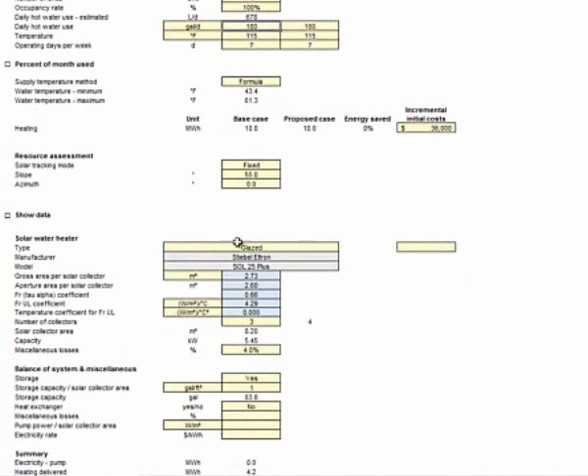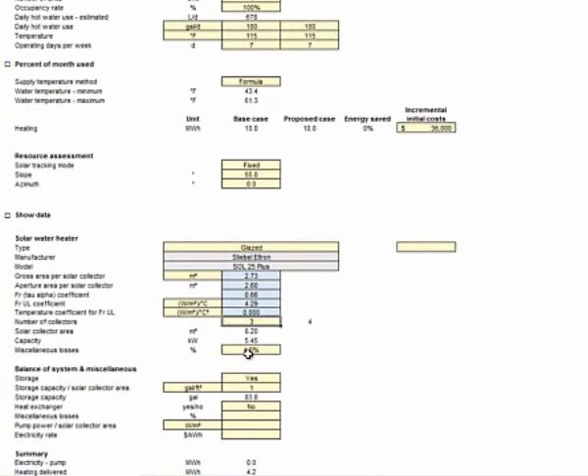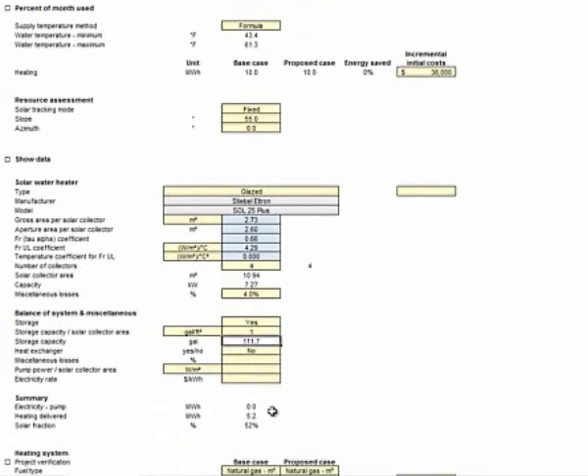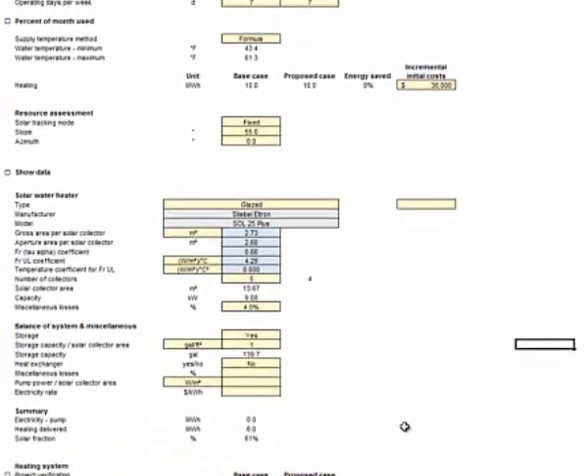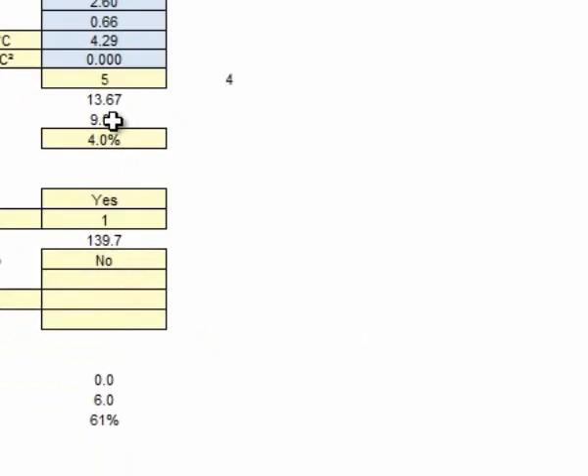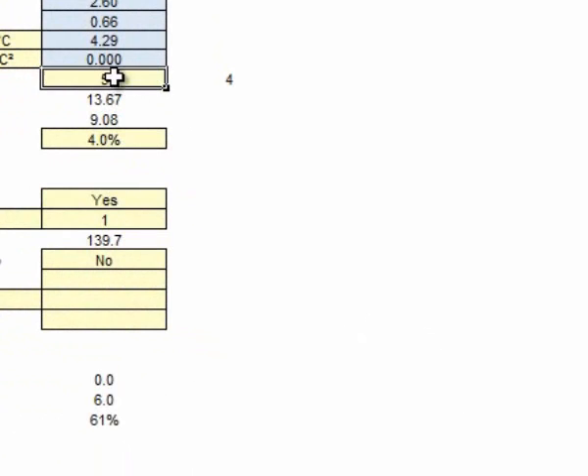Now what this thing is doing for us though is the number of collectors has now gone up and it's been changed. So now let's go back to 4. That brings me back to 111.7 gallons. That's only going to cover about 52%. So let's go up a little bit. Let's make it 5. Now I have 140 gallons.